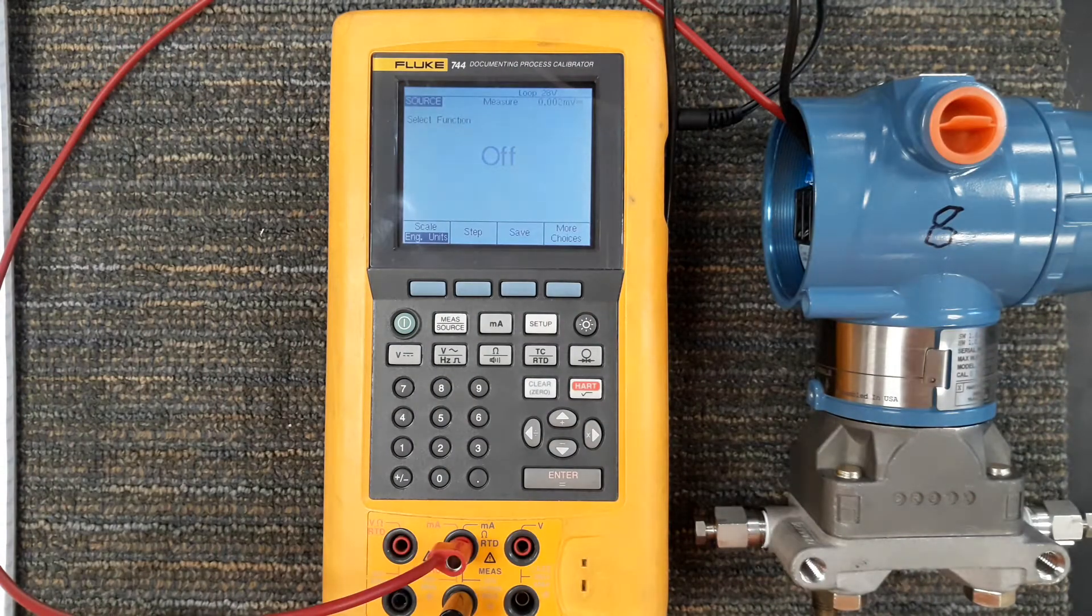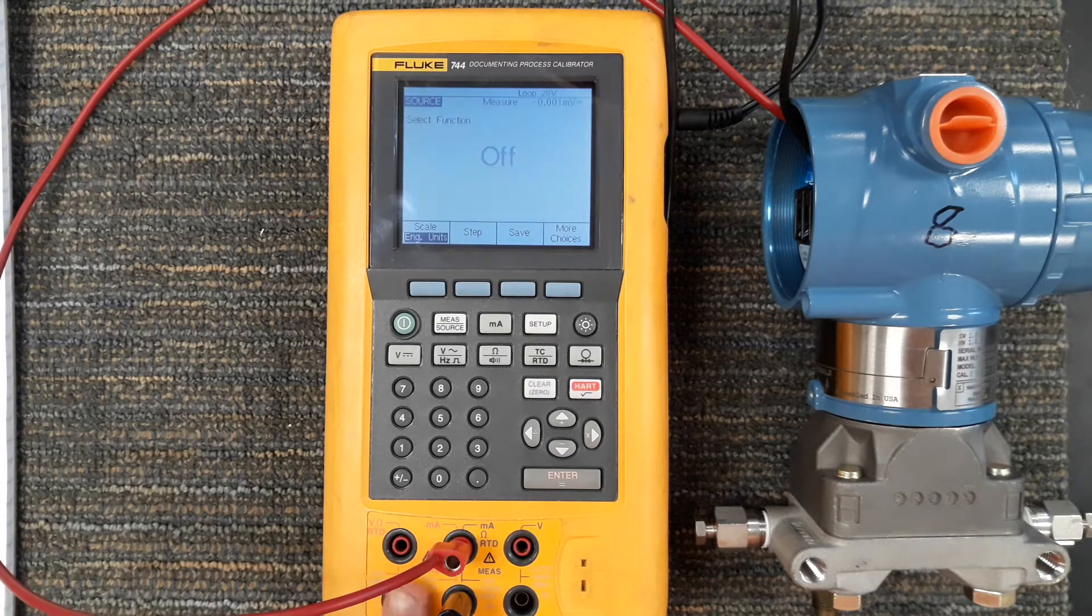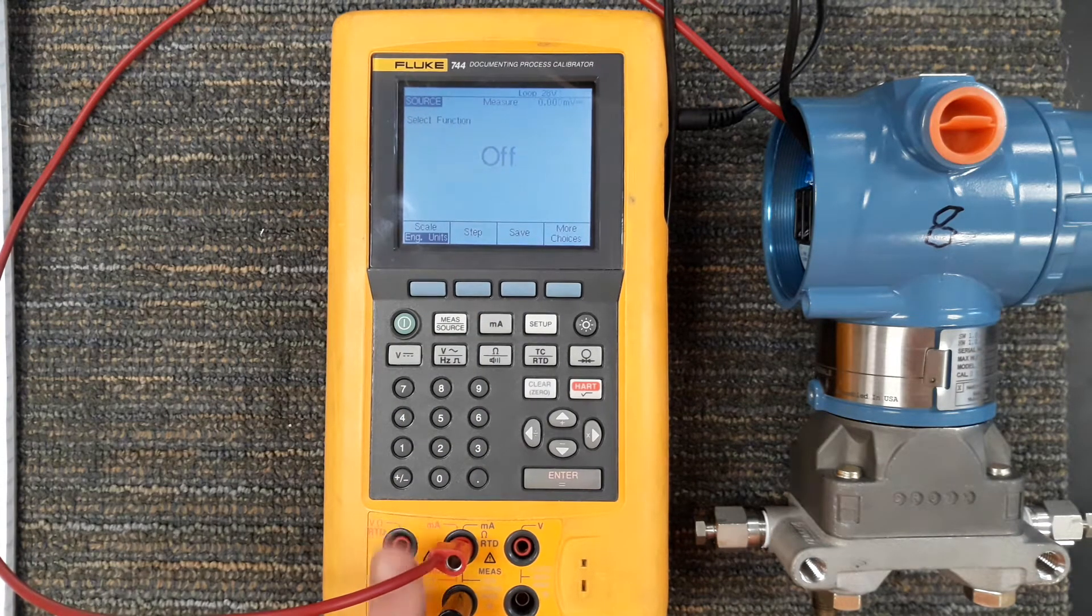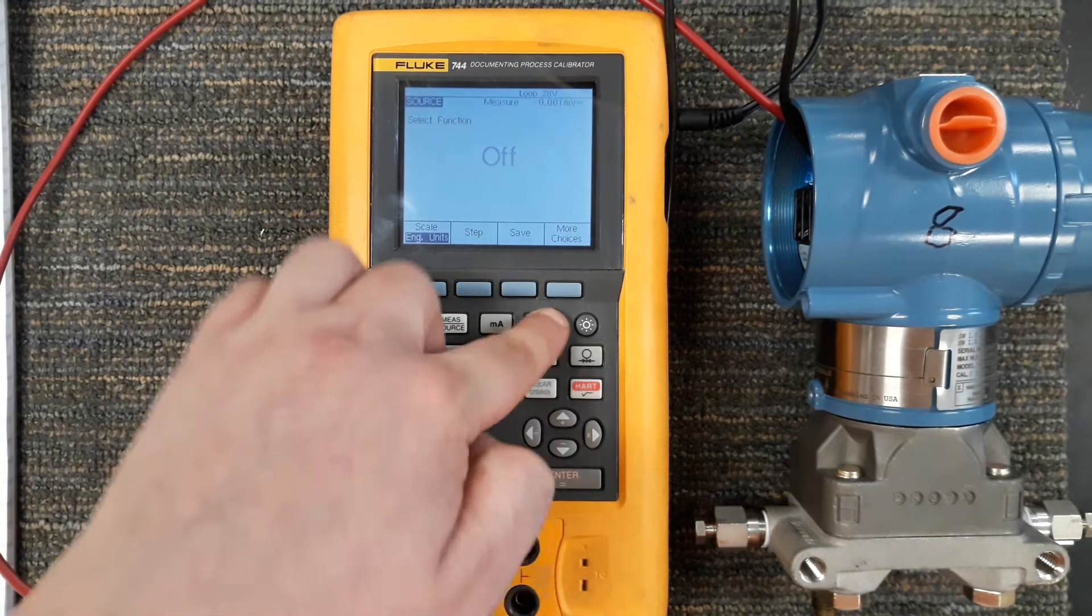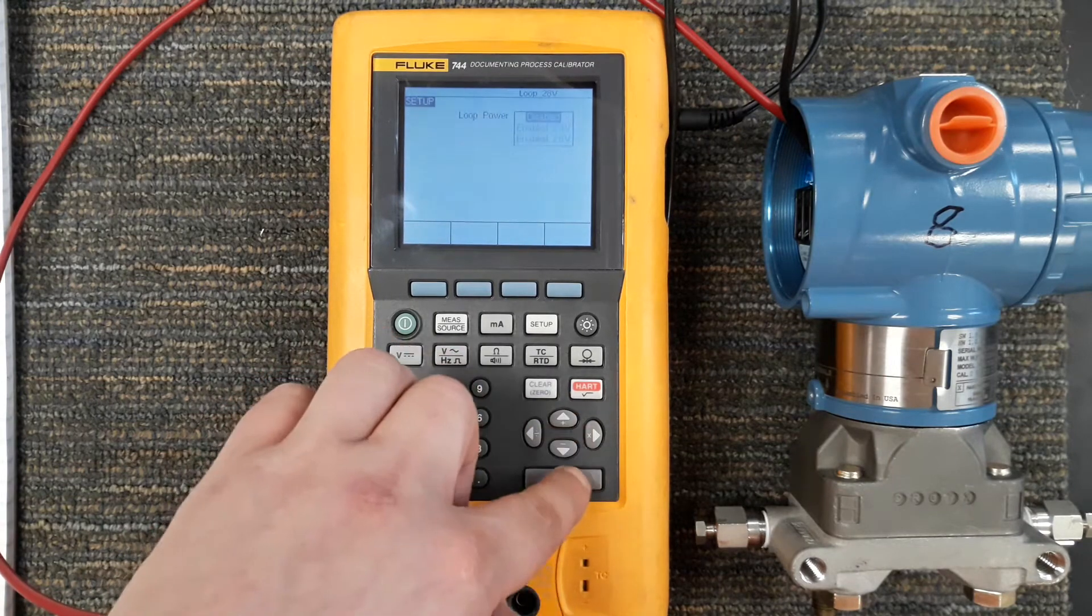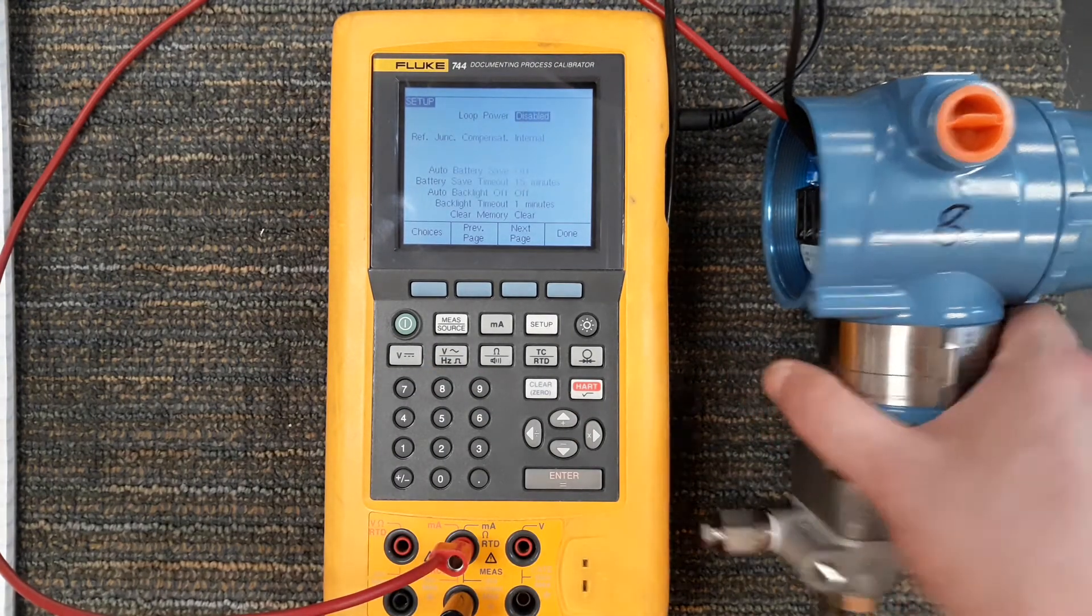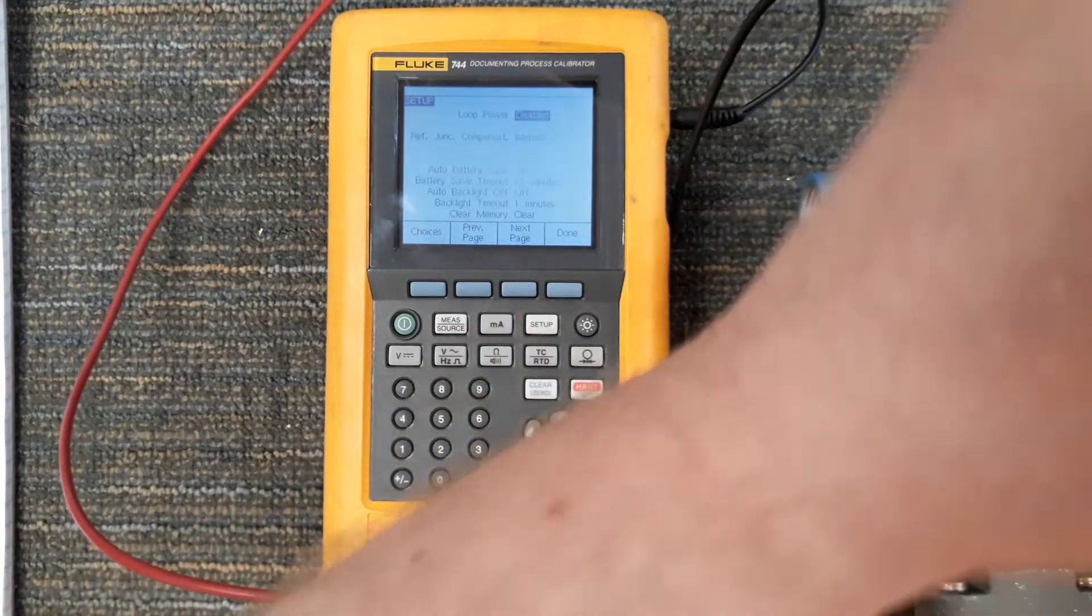Again using the milliamp ports for sourcing current to provide loop power, do not use the voltage ports it won't work. I'm gonna go ahead and go back into setup and disable my loop power. Now that it is disabled I'm going to go ahead and lift my power wires for my transmitter.